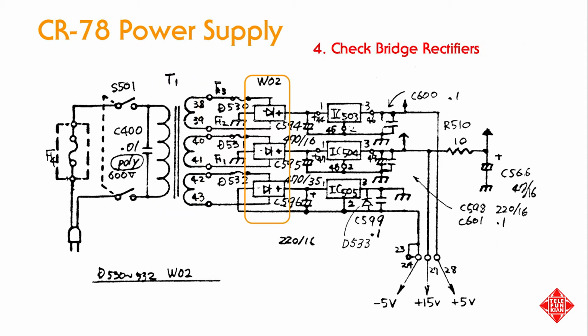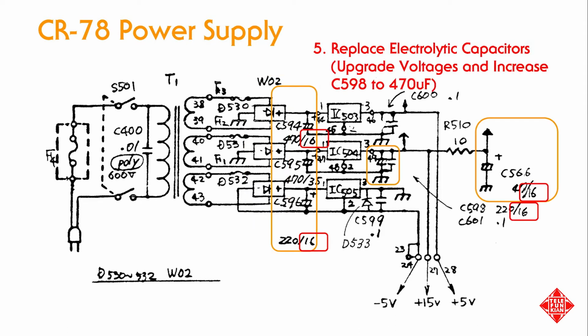The three bridge rectifiers will be checked to ensure that the proper voltage drops are present across each terminal, that the rectifiers are functioning as 4 diodes in bridge configuration, and there are no opens, shorts, or failing diodes. All of the electrolytic capacitors in the power supply will be replaced with new capacitors, as they're more than 40 years old at this point. We'll also be upgrading them slightly.